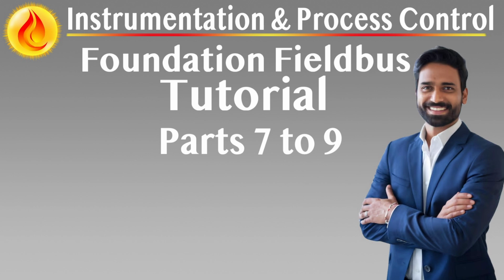Finally, SMP plays a central role in device replacement strategies. By retaining and mapping PD tags, node addresses, and block configurations, it supports plug-and-play replacement of faulty devices. When a replacement device is detected with a matching device ID or profile, SMP can automatically assign the correct address, download the appropriate configuration, and reintegrate the device into the network with minimal disruption.